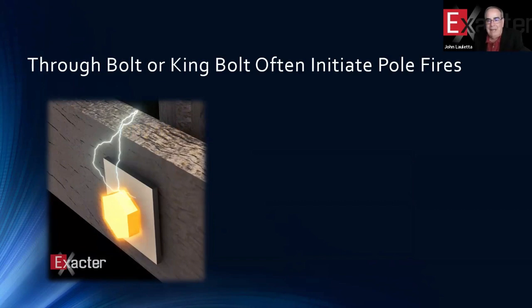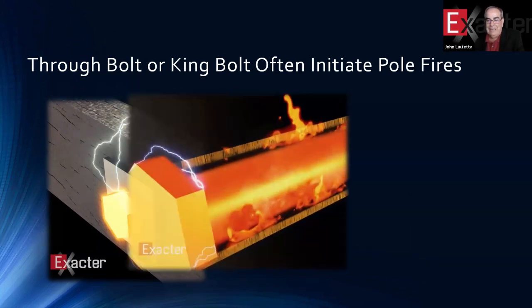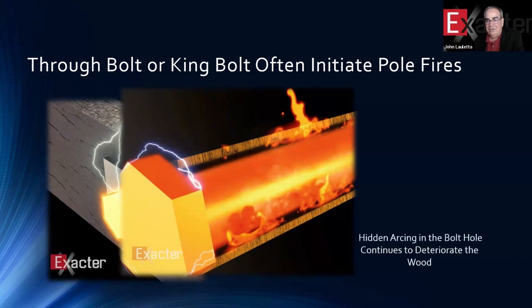Now, I mentioned that the metallic components on the pole are really where the problem is going to center itself. And of course, it's the lowest impedance part of the system, right? So the currents collect, if you will, at the king bolt. And when the king bolt gets warm, it accelerates the drying out of the cross arm at that point. And now you get partial discharge from that interface between the wood and the bolt that's no longer tight. It's now loose because the wood is shrinking away from the bolt. And it continues to deteriorate right there.